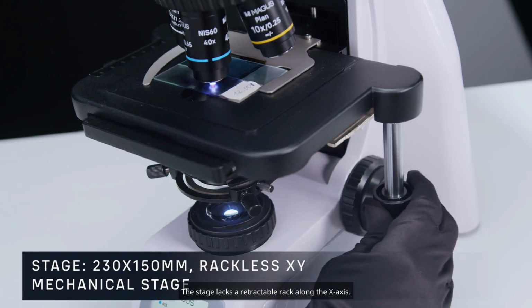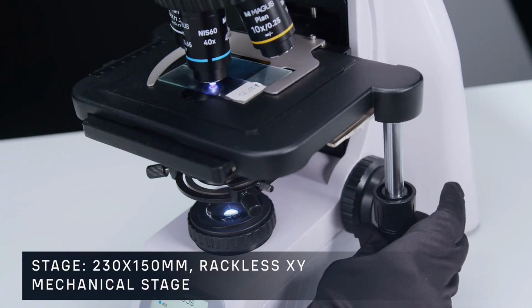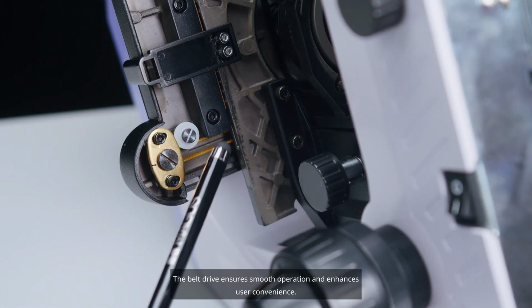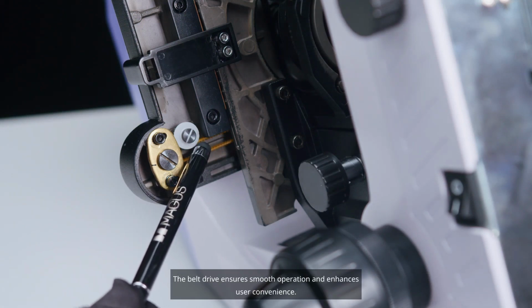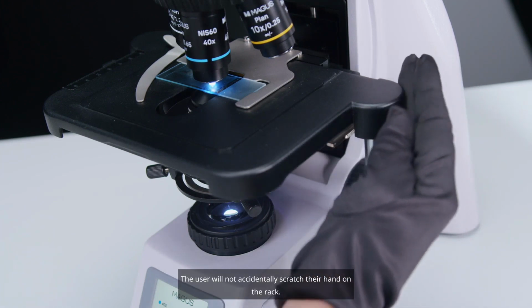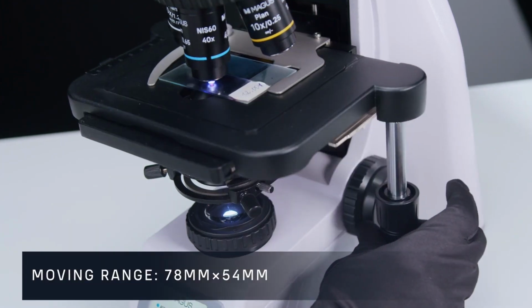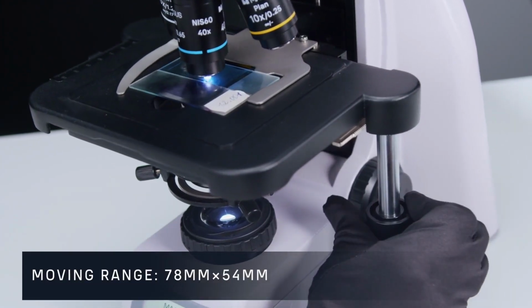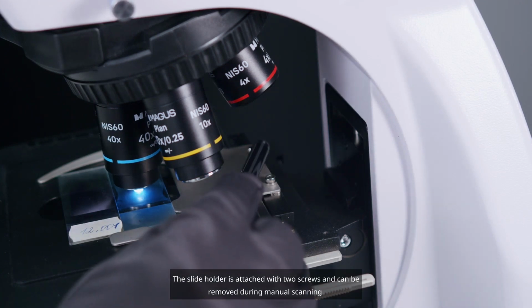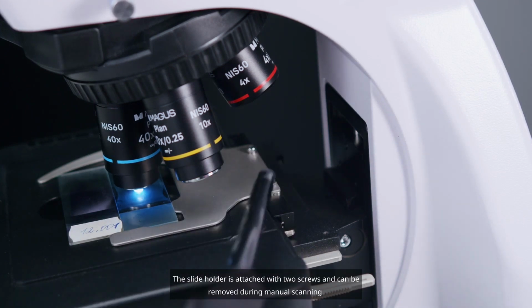The stage lacks a retractable rack along the x-axis. The belt drive ensures smooth operation and enhances user convenience. The user will not accidentally scratch their hand on the rack. The slide holder can secure 2 slides. The slide holder is attached with 2 screws and can be removed during manual scanning.